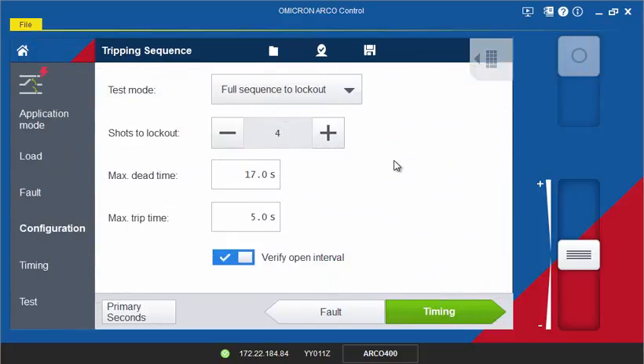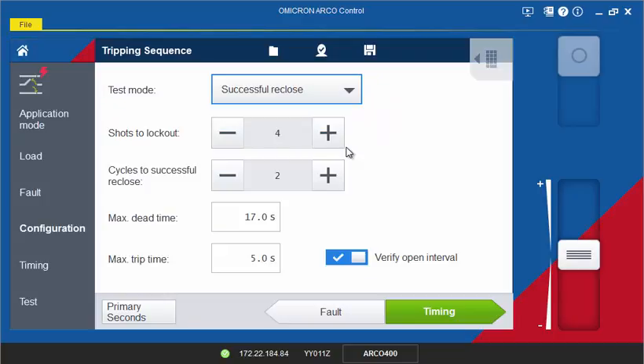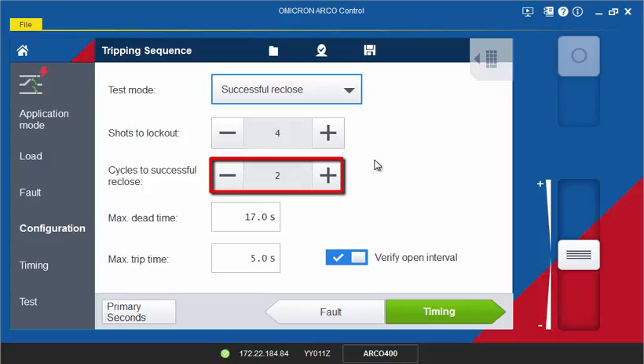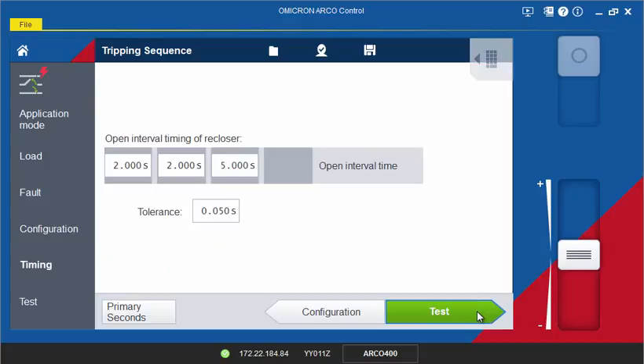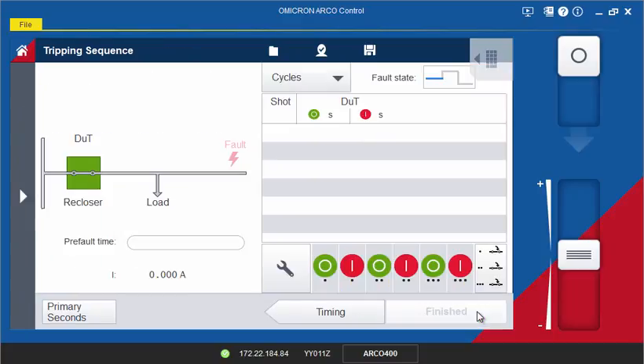The successful reclose test mode is configured similarly. Enter the number of cycles after which a successful reclose will be simulated by outputting the nominal load state instead of another fault. The other settings are the same as they are in the full sequence to lockout test.